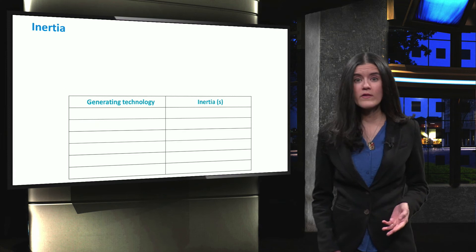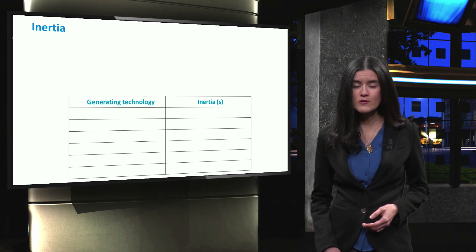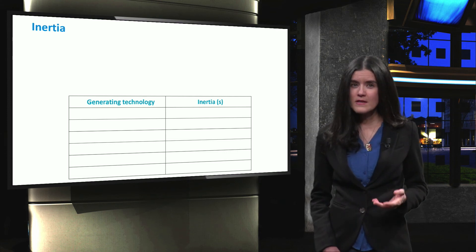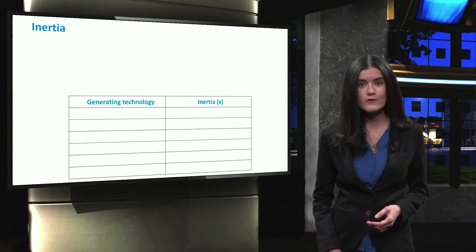Any generator with a rotating mass that is directly connected to the grid provides the inertial response inherently. This effect cannot be obtained if the generator is connected via a power-electronics interface.